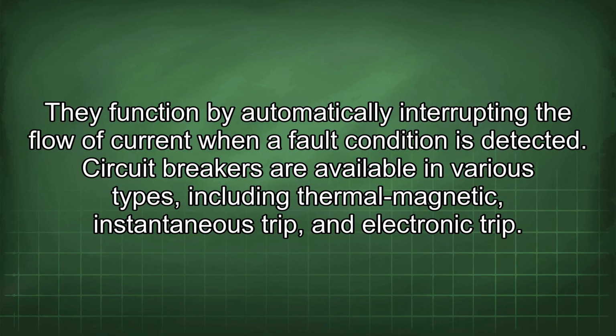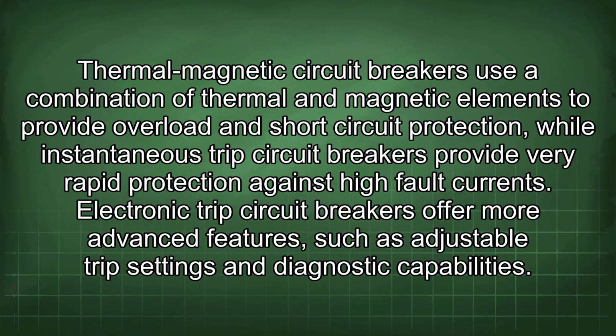Circuit breakers are available in various types, including thermal magnetic, instantaneous trip, and electronic trip. Thermal magnetic circuit breakers use a combination of thermal and magnetic elements to provide overload and short circuit protection, while instantaneous trip circuit breakers provide very rapid protection against high fault currents. Electronic trip circuit breakers offer more advanced features such as adjustable trip settings and diagnostic capabilities.